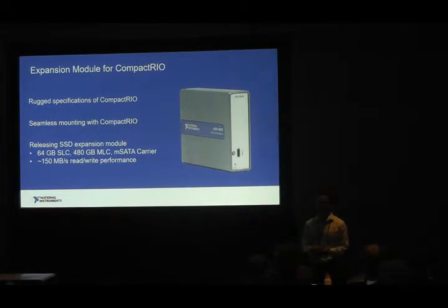We have a similar DIN rail option like we do with CompactRIO, and also a panel mount option, so you can mount this directly next to the device. For the SSD, one, this will be one of the highest read-write performances that you can get out of a controller. And two, we're going to have several options. There will be a 64 gigabyte SLC option, which is really good for high endurance within rugged environments, especially across a very high temperature range.